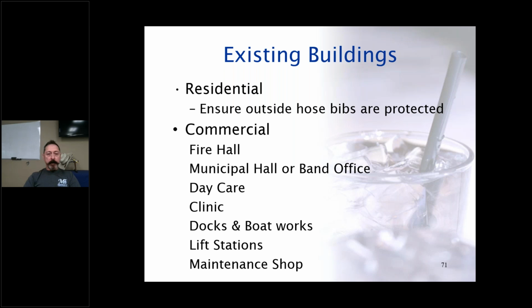For smaller utilities, if it's just residential, that's 90% of your facility or your community, then let's focus on those hose bibs, right? Let's make sure that all the hose bibs are protected. Now, one note, if they're built in, these are self-draining, that's fine. If you're going to thread one on, they make an indoor one and an outdoor one. It's important to put the outdoor one on because that allows the hose bib to drain so it won't freeze. Those are frost-free hose bib or hose connection vacuum breakers. So we want to make sure those are frost-free. Otherwise, if you put the wrong one on, we're just going to freeze a lot of hose bibs. So watch out for that. But they're relatively inexpensive, $25, $30, $35, somewhere in there. And that's half, or 3/4, of your cross connection program, isolating hose bibs in a small community. So it's not an onerous thing to achieve and can be done.